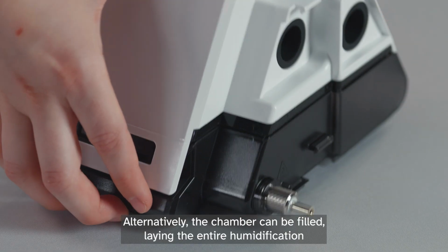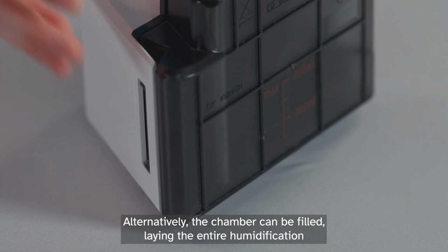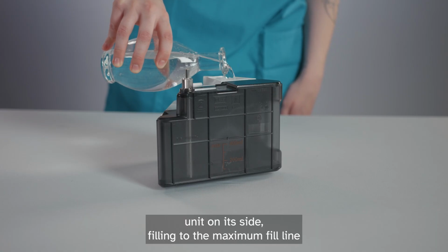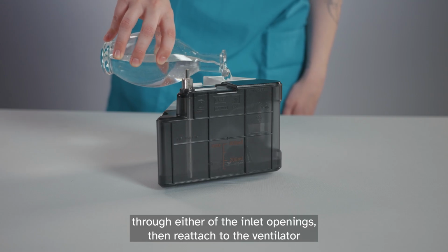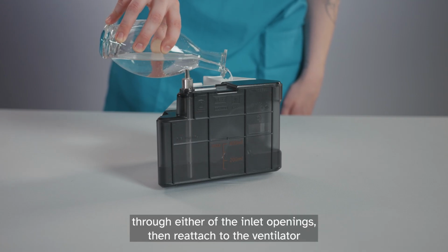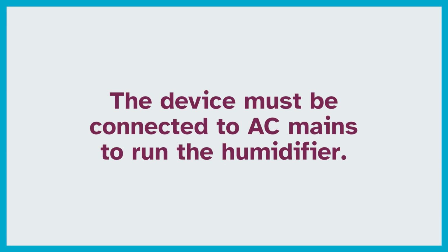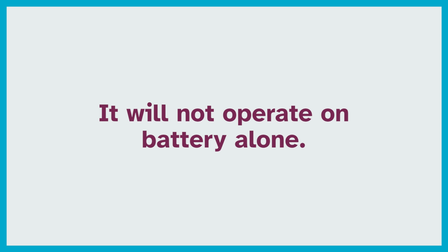Alternatively, the chamber can be filled by laying the entire humidification unit on its side, filling to the maximum fill line through either of the inlet openings, then reattaching to the ventilator, clicking it into place. The device must be connected to AC mains to run the humidifier. It will not operate on battery alone.